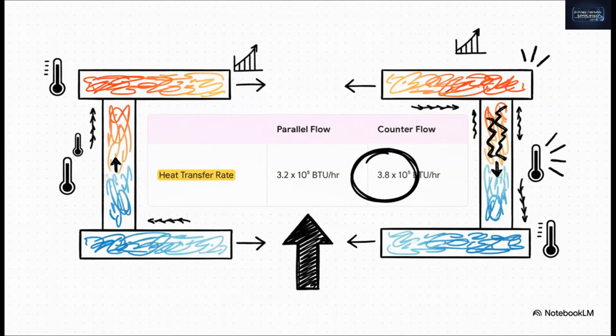In the exact same setup, the parallel flow design moves about 320,000 BTUs per hour. A BTU, by the way, is just the energy it takes to heat about a pound of water by 1 degree Fahrenheit. Now look at counterflow, 380,000 BTUs per hour. That's a huge jump in performance, and it's all because it keeps that average temperature difference higher across the entire device. It just works better, plain and simple.